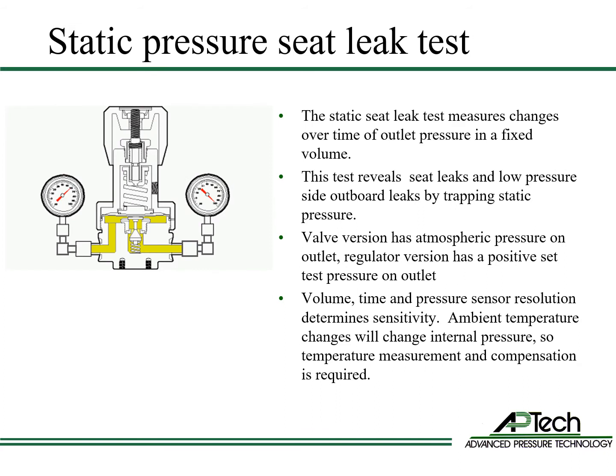Valve and regulator seat leaks are also tested using static pressure. This test can use any gas and measures changes over time of the outlet pressure in a fixed volume. This test reveals both seat leaks and low pressure side outboard leaks by trapping static pressure. The valve version of this test usually has atmospheric pressure on the outlet. The regulator version adjusts the outlet pressure to a given positive test pressure setting. Test sensitivity is determined by trap volume, pressure sensor resolution, test pressure, and time. Ambient temperature changes over time will also affect test accuracy, so temperature measurement and compensation is required. Many customers perform this test after helium leak testing and also before system startup.